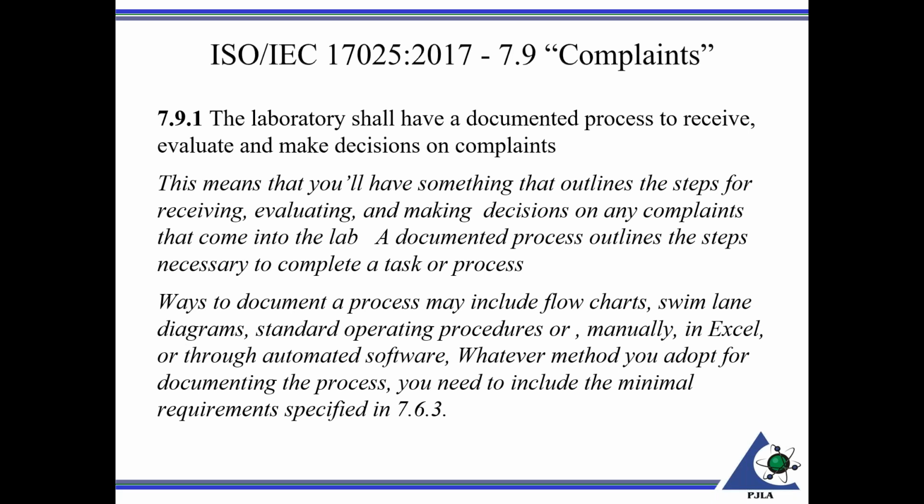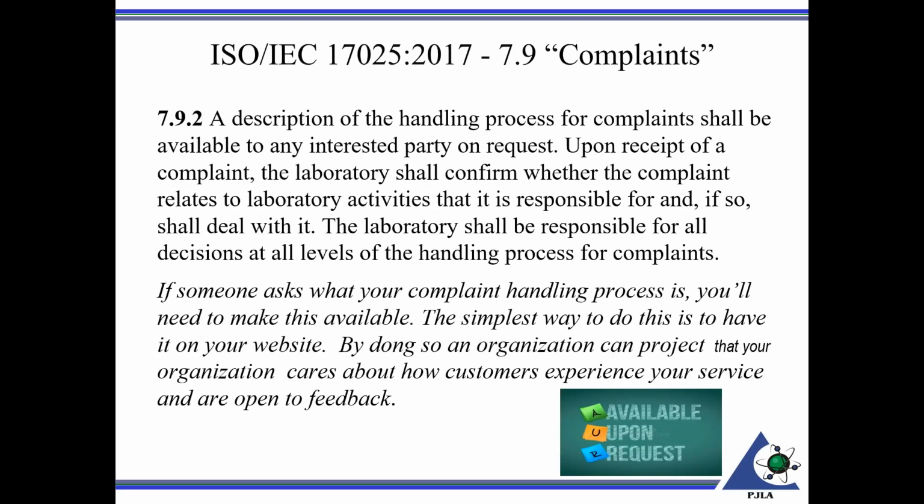Somewhere in your quality management system, specifically concerning complaints, a process should be documented and followed when those situations arise. 7.9.2: A description of the handling process for complaints shall be available to any interested party on request. Upon receipt of a complaint, the laboratory shall confirm whether the complaint relates to the laboratory activity that it is responsible for, and if so, shall deal with it. The laboratory shall be responsible for all decisions at all levels for the handling process for complaints.